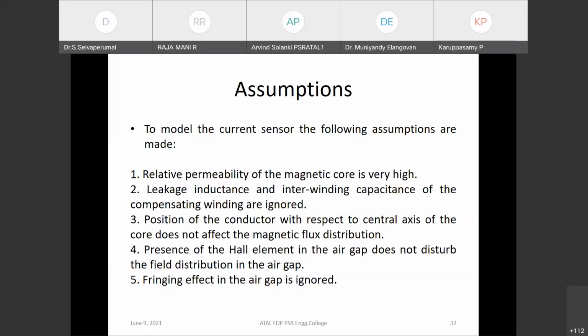Hall effect current sensors are mostly used to sense switching ripple currents of switching converters, grid frequency currents and their harmonics. The typical bandwidth of a Hall effect current sensor is 200 kilohertz, while switching frequency in power electronic converters may go up to 100 kilohertz. The non-idealities associated with the sensor become significant at frequencies greater than hundreds of kilohertz, so the above assumptions are relevant from the perspective of power electronic applications.